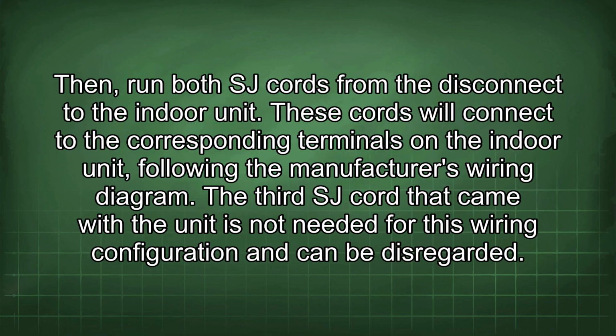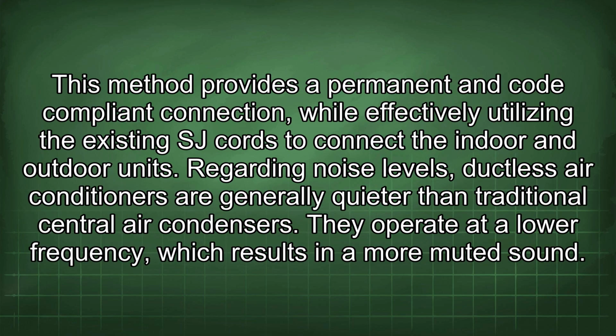Then run both SJ cords from the disconnect to the indoor unit. These cords will connect to the corresponding terminals on the indoor unit following the manufacturer's wiring diagram. The third SJ cord that came with the unit is not needed for this wiring configuration and can be disregarded.